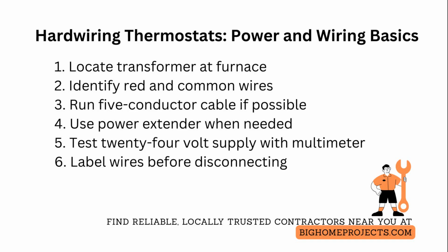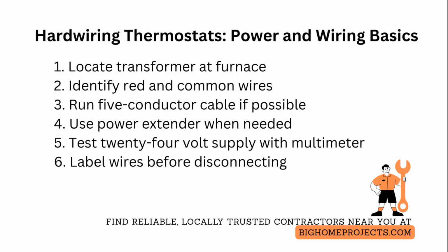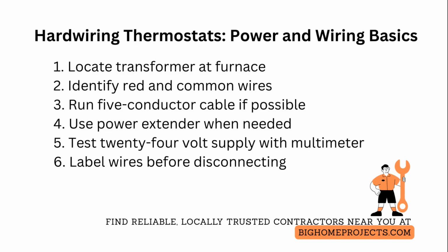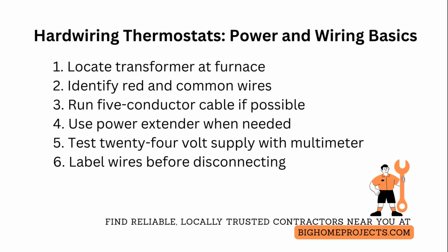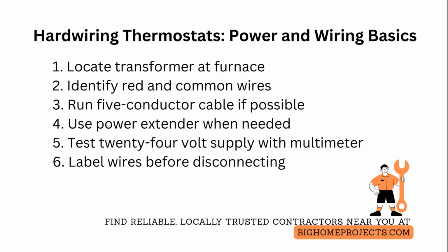If you only have 2 wires, you can still add a common by fishing a new cable or installing a power extender kit at the air handler, which is a proven workaround when running new cable is impractical. Test the control board terminals with a multimeter first to confirm you have a stable 24-volt AC supply and that the common is not switched. Unstable voltage or a floating common causes intermittent powering or system confusion.